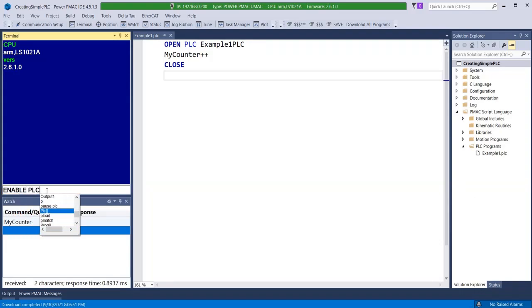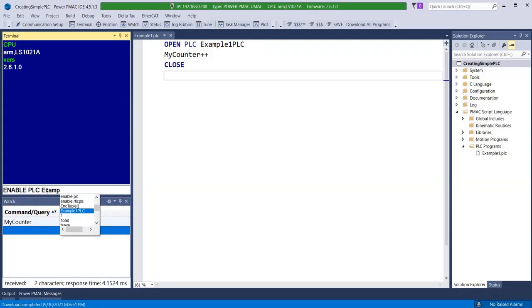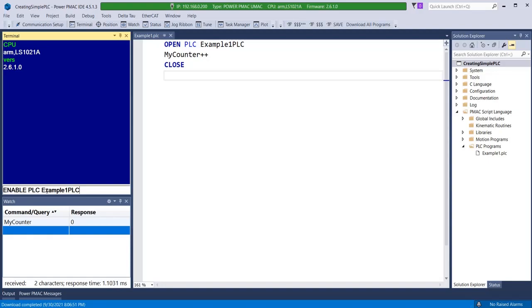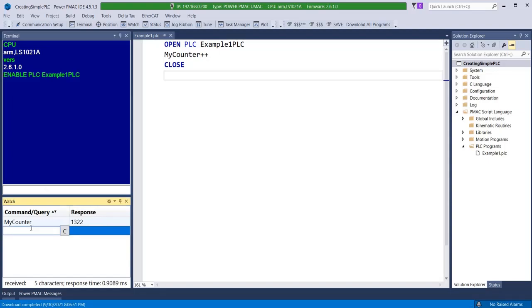Caution is generally advised here, especially for beginners or machine integrators developing new PLCs that may contain motor motion or other mechanical functions because the PLC will start scanning immediately after it is enabled. MyCounter now increments very fast every time example 1 PLC is scanned in the background.